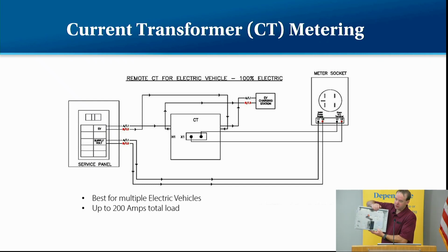The nice thing about the CT metering is you can have multiple chargers as long as the total load is less than 200 amps. So you could have 2, possibly 3 car chargers on one meter. There's not too many households that have just one vehicle right now, and if you're out there to put in one EV and they've got 2 vehicles, they're probably going to be getting a second one down the road. So this might be a good way to go. Unless they're going the ZEF Energy route, this might be a good way to go for planning for the future. If you do have more than one EV, if you've got A phase coming from the left and B phase coming from the right on one charger, you just have to match that with the other chargers.